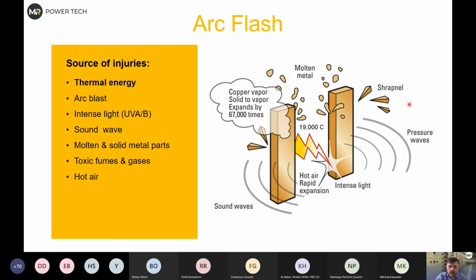If you have an arc fault inside the switchgear, as you saw on the video before, you'll see a lot of small particles flying all over, those blinking things. They are relatively small in size, but let's say shrapnel, solid objects from the bus bar, may reach up to 1,100 kilometers per hour speed, which is a lot. But because they are very small size, they're usually not considered straightforwardly deadly—you'd need to be very unlucky, for example to be hit in the eye, if you don't wear eye protection at all.